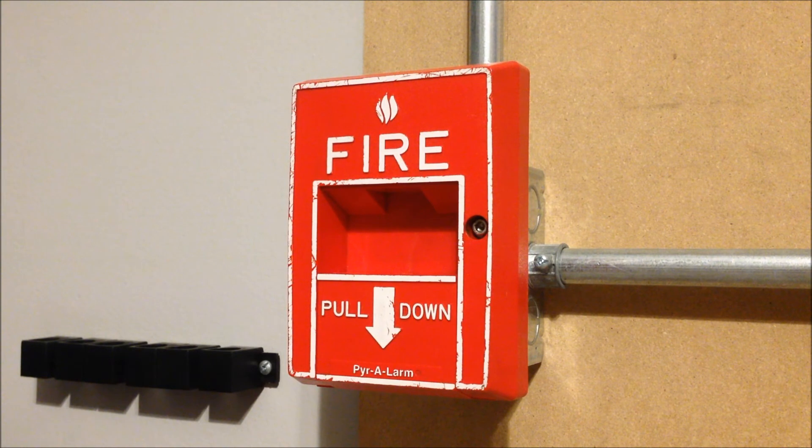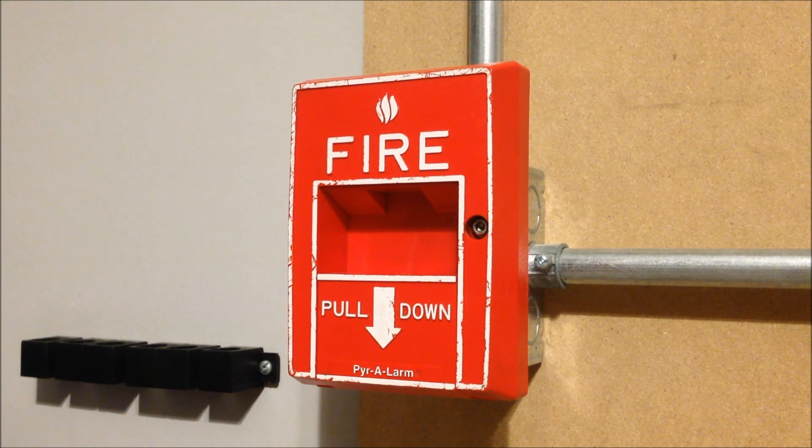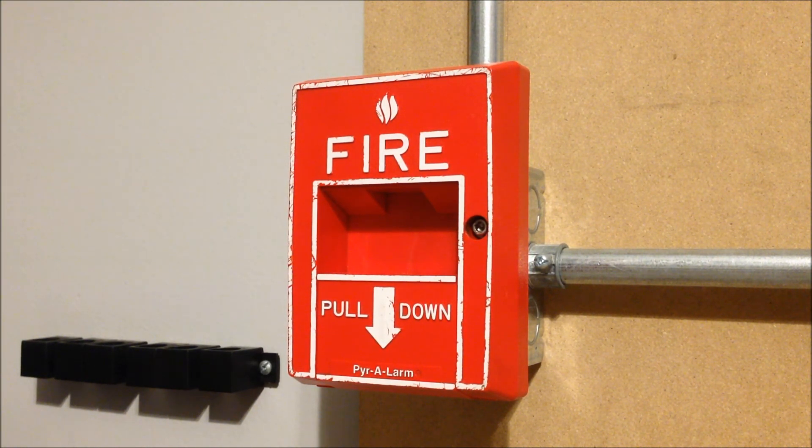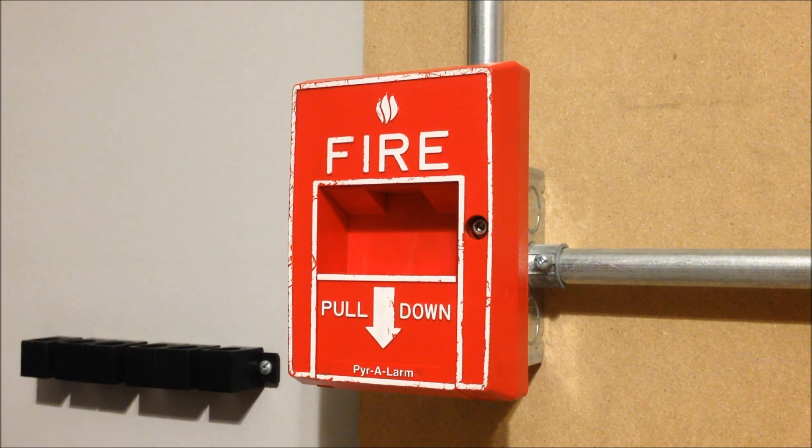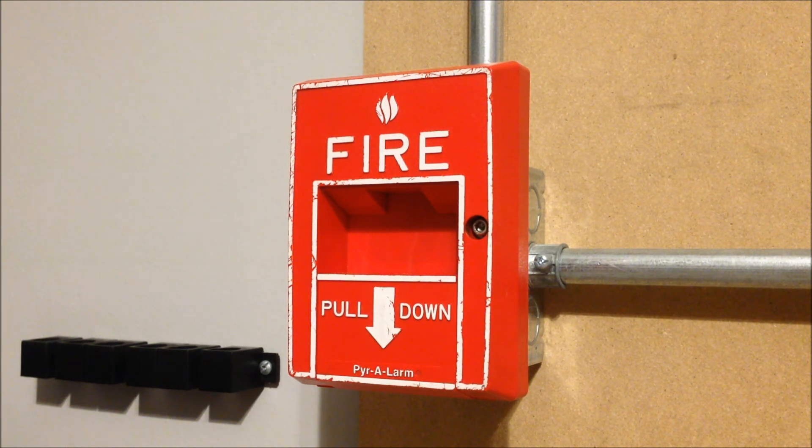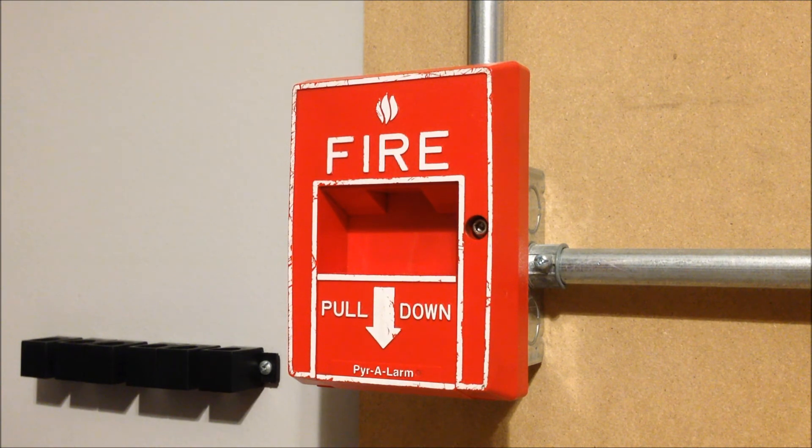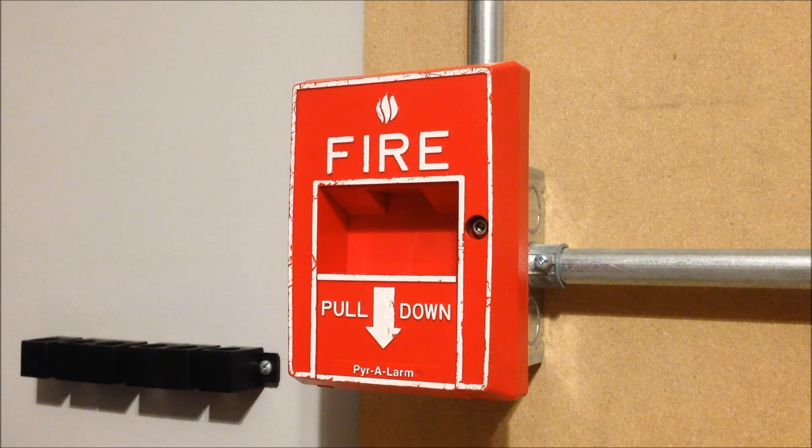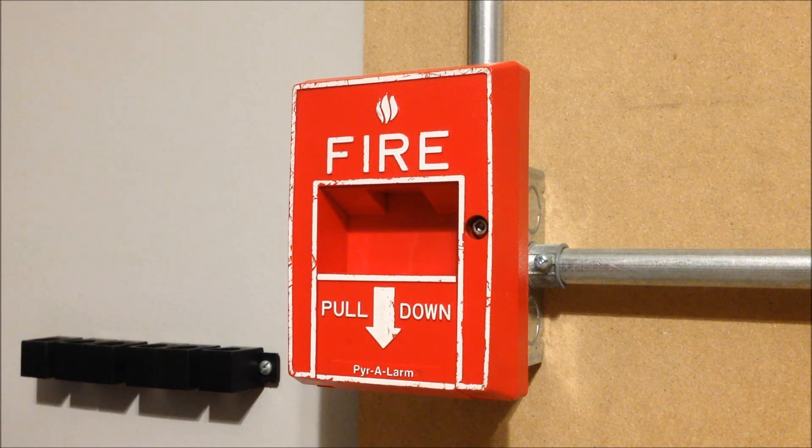So we're going to start things off today with the Pyr-A-Larm station. So this is wired into zone 2 on the panel. And since I have the NAC programmed to simple zone code, when I pull this, you're going to hear it start chirping out two short beeps every few seconds on this chime to indicate that zone 2 has gone into alarm.